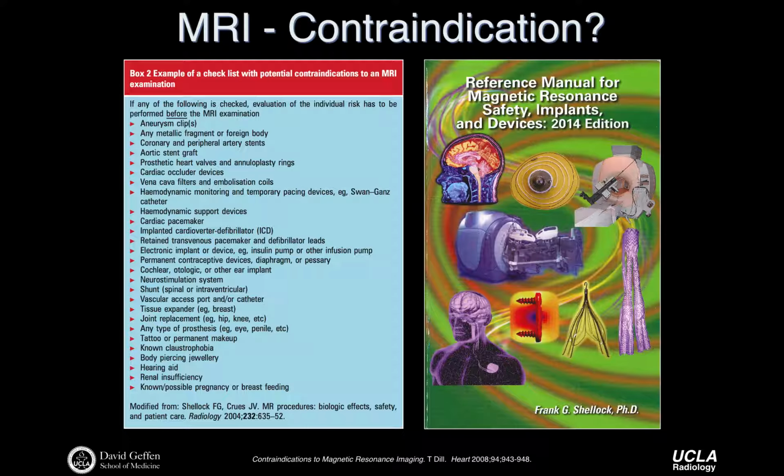There is a great book here that you can check out if you really get into MR safety. My group does a little bit of MR safety research. Frank Shellock is the godfather. He's built his career all around MR safety and every year publishes a new version of this handbook. Point being, if you were in a research environment or a clinical environment and a patient had a particular device implanted, you can go to his handbook and find out what's known or not known about that particular device and the safety or the risks associated with imaging the patient.